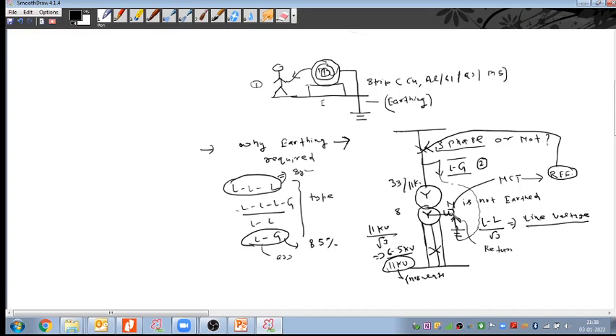Now you can ask me what should be the NCT rating in that case. How do we decide the NCT rating? The general practice is to take how much current is flowing on the phase side when no fault happens, and the NCT rating we can select the same as the phase CT. If this is 600 by 1, we can also take a 600 by 1 CT here. This is how we can decide the NCT rating.